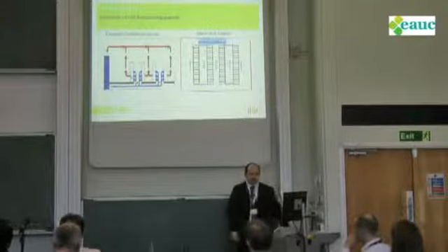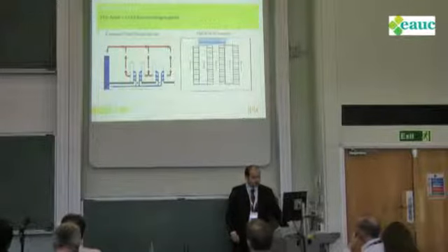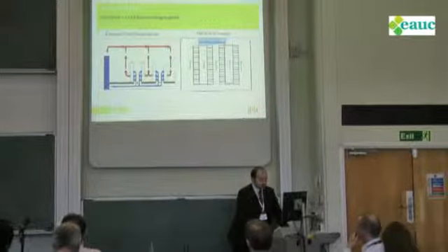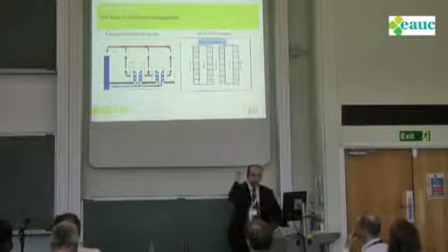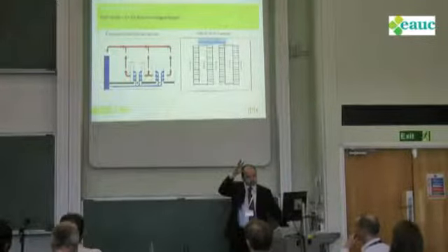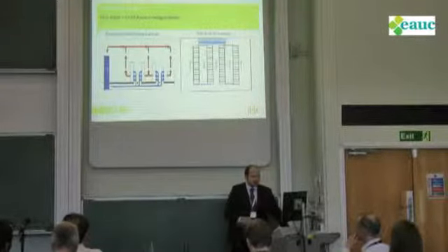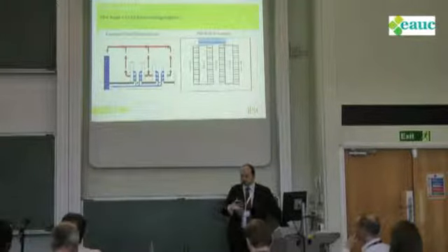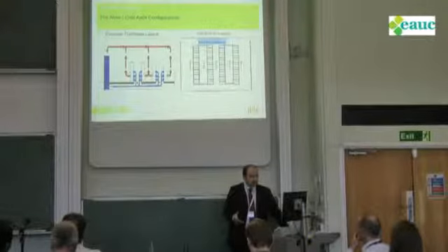Typically the temperature will change by about 10 degrees going through the servers, so it comes out the back 10 degrees warmer. Using natural convection, that goes up to the ceiling. Sometimes people will have a full ceiling as well to take the hot air away, and then that returns back to the handling unit where it is cooled again. That's the cycle. That's a traditional layout.